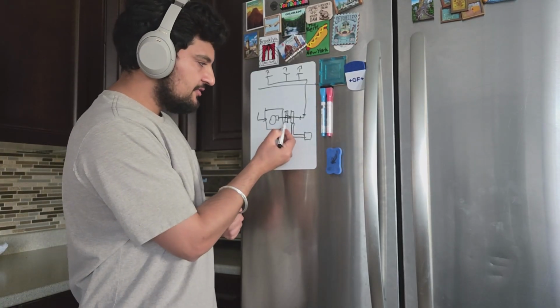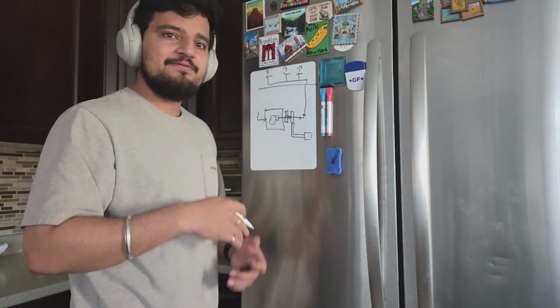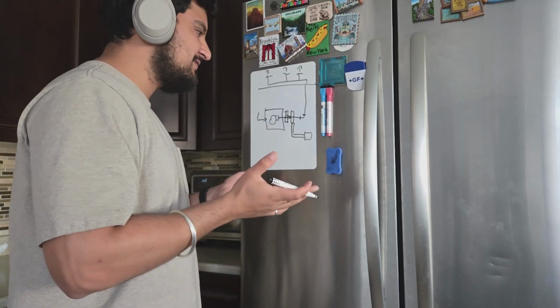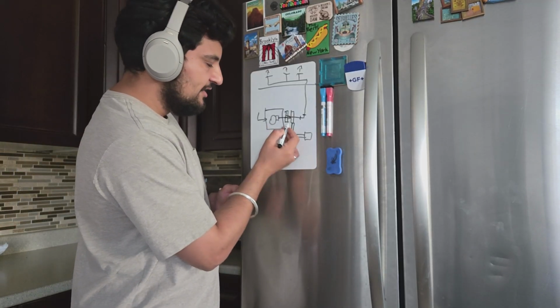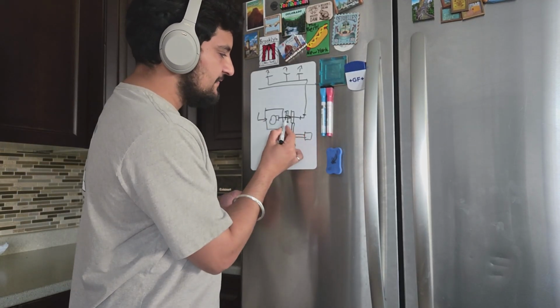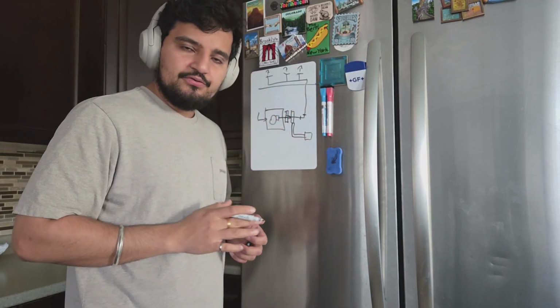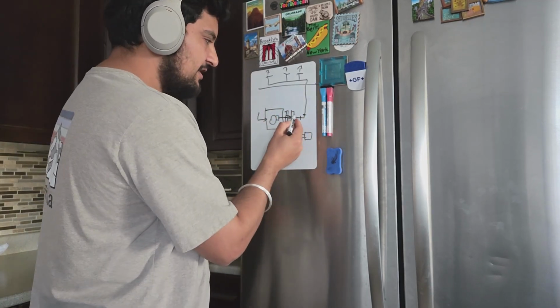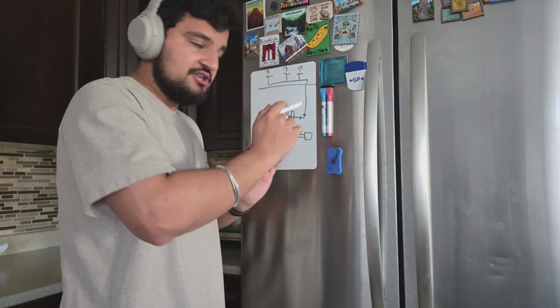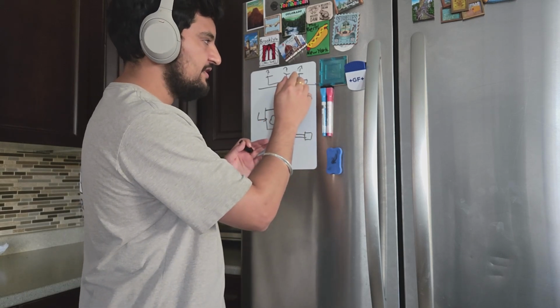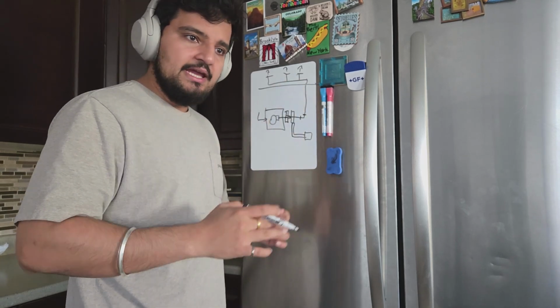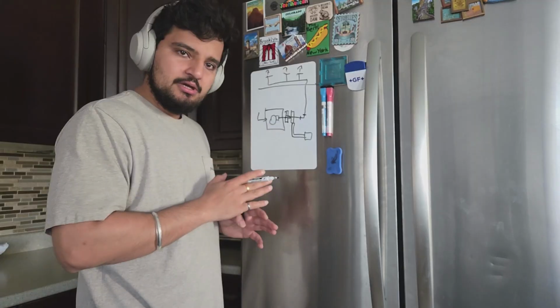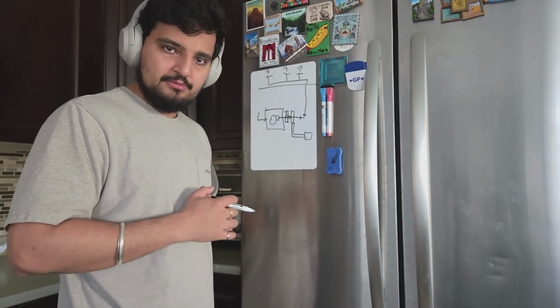So the filter has some amount of pressure loss. As the filter gets dirtier, the pressure loss increases. The cooling coil has an amount of pressure loss. There's friction loss of the air through the ductwork. And also every time the air has to, for example, change direction through an elbow or go through these registers into your room, it loses a little bit of that energy through friction, another phenomenon, right?